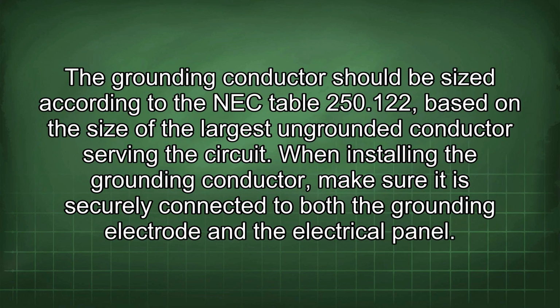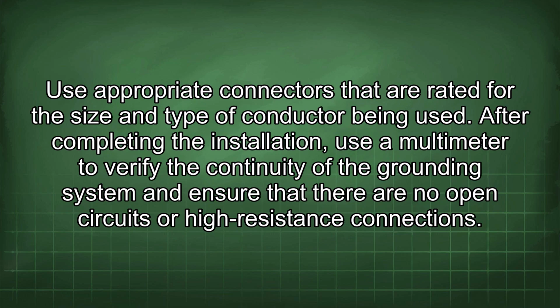The grounding conductor should be sized according to NEC Table 250.122, based on the size of the largest ungrounded conductor serving the circuit. When installing the grounding conductor, make sure it is securely connected to both the grounding electrode and the electrical panel. Use appropriate connectors that are rated for the size and type of conductor being used.